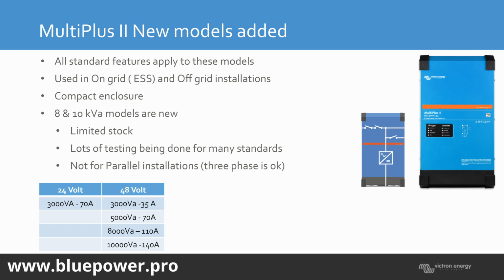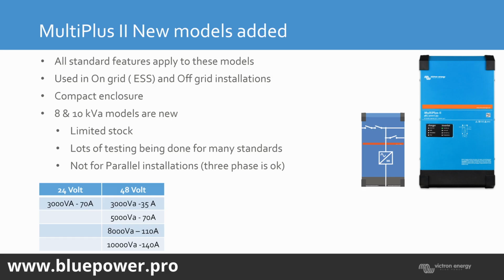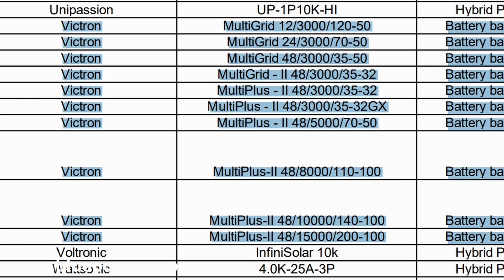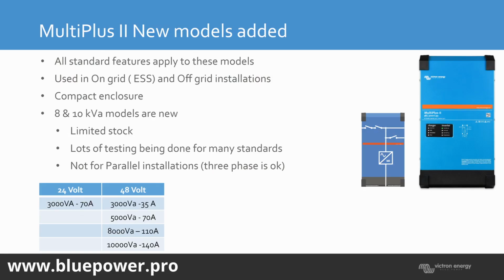On the Multiplus II, that's the inverters that's got the NRS 097 compliance. So those are the ones that's required to be installed in the City of Cape Town. They range from 3 kVA up until 15 kVA now. The 8, 10 and 15 kVAs got released this year, and then the NRS approval, or their NRS certification also got approved about 1 month ago, and they're going to be loaded onto the City of Cape Town's list within this month. And these already?